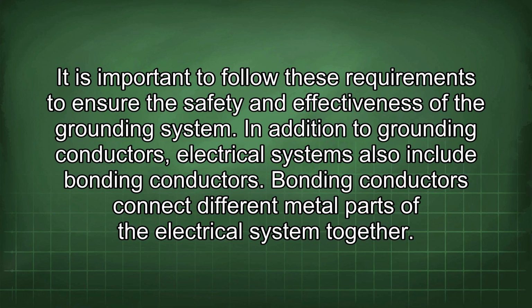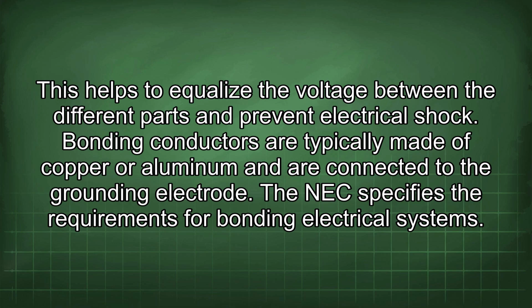In addition to grounding conductors, electrical systems also include bonding conductors. Bonding conductors connect different metal parts of the electrical system together. This helps to equalize the voltage between the different parts and prevent electrical shock. Bonding conductors are typically made of copper or aluminum and are connected to the grounding electrode.